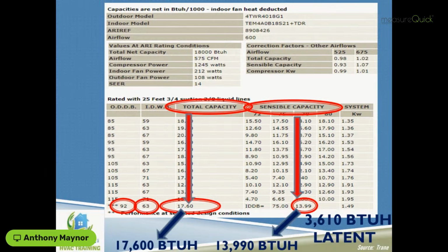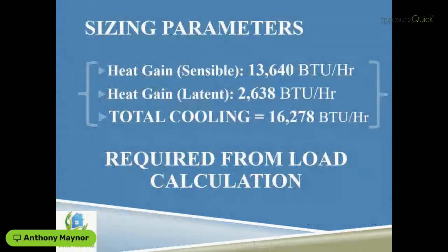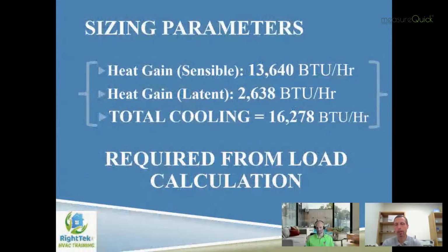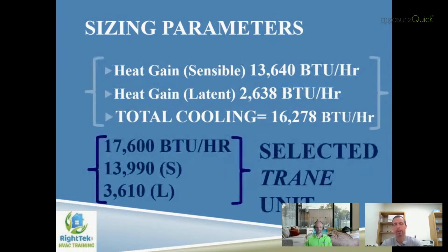So how would I apply this using the current Manual S? Well, I go to my current load calculation. For cooling, I've got my sensible and my latent gain, and I want to add those together to find out my total cooling load. That comes up to about 16,278. I know this is a little bit math intensive, so humor me for a minute here. What you see in white at the top of the slide is the load calculation numbers, the heat gain from my Manual J. And what you see in dark blue down below is the interpolated performance data that I just derived from my OEM's expanded performance data.